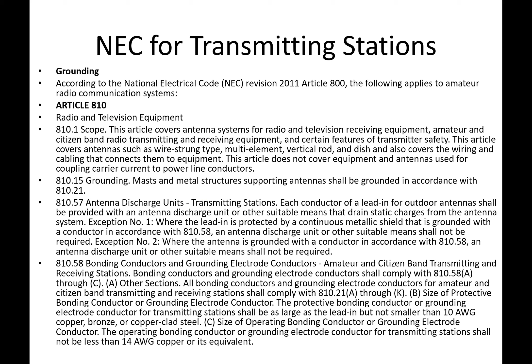Yeah, no doubt about that, John. I like 12 gauge wire. All my extension cords that I personally own are 12/3s, for the same reason—they conduct a little more electricity and more current, and 14 gauge is kind of small. But that's NEC code, so I wanted to quote it. Yeah, there's no reason not to exceed specification. Grounding wires should be 6 gauge, 8 gauge kind of stuff, because you're potentially conducting a lot more current to ground than the standard service coming into your building. Any other observations or questions before I proceed?